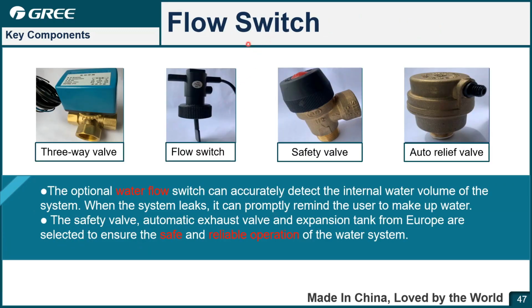And next one, flow switch. 3-way valve to control the flow direction to water tank and floor heating and FCU. Flow switch to detect the water flow to make sure there is sufficient water inside and prevent some freezing. Safety valve, in case of over high pressure inside, it will release the pressure. This is for the air discharge.